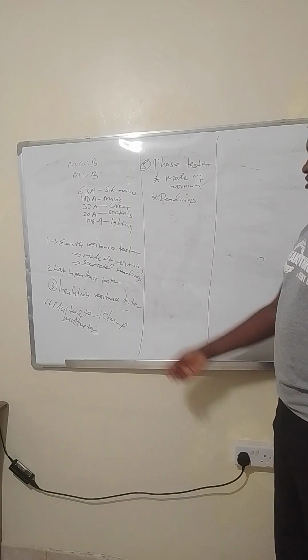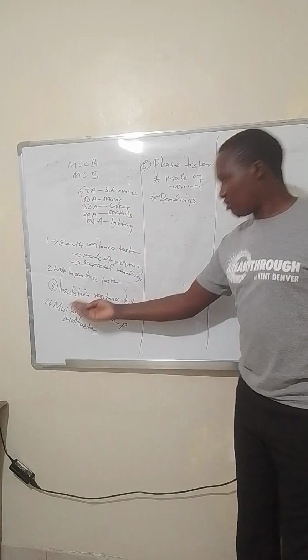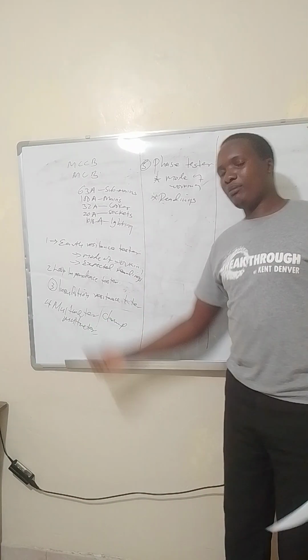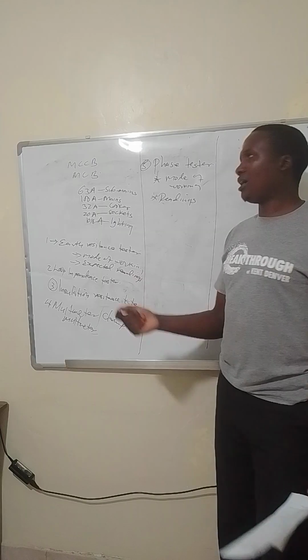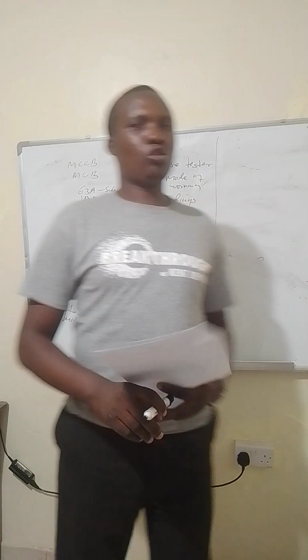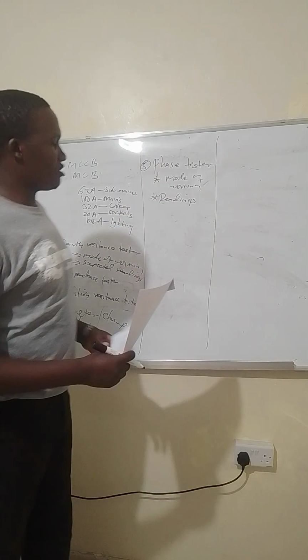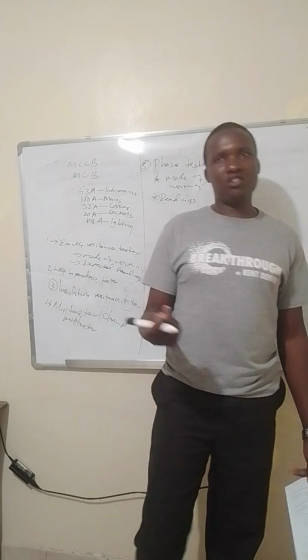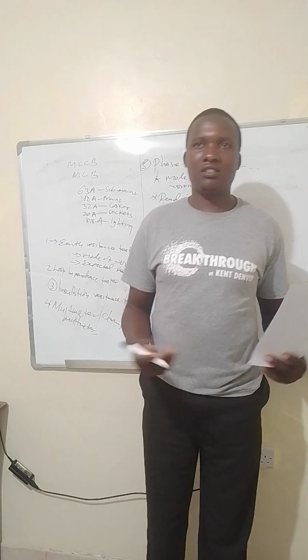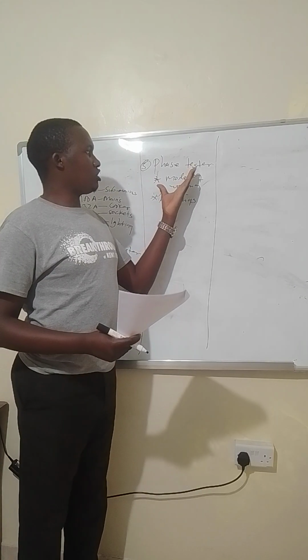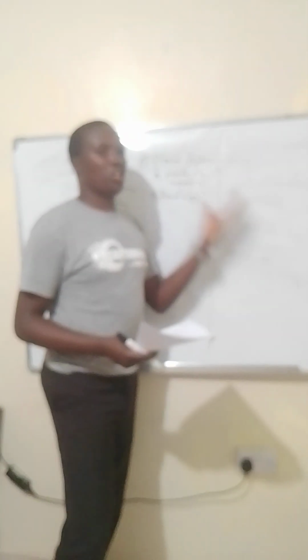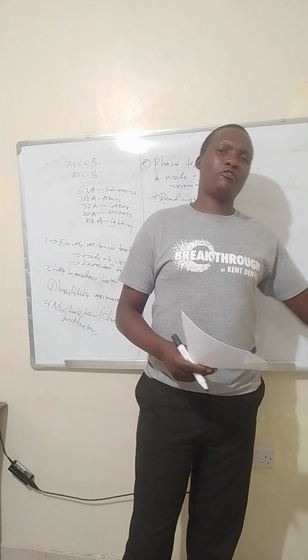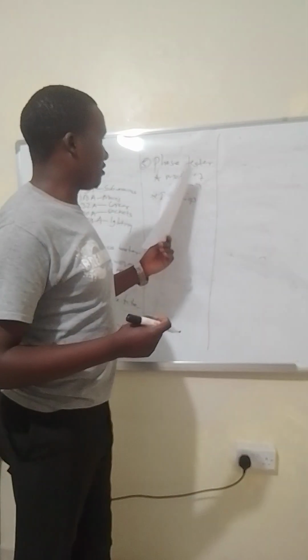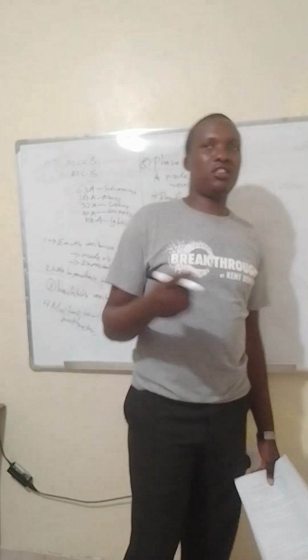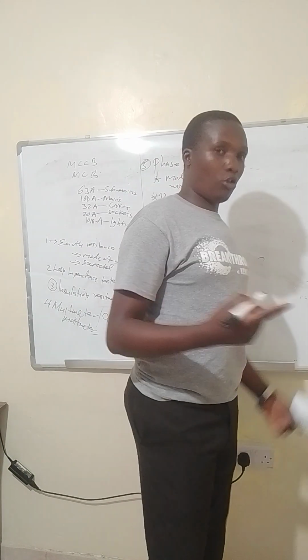We have earth resistance tester, we have loop impedance tester, we have insulation resistance tester, we have multimeter or clamp multimeter. They work hand in hand. We have phase tester. So you need to know very well the function of a phase tester. A phase tester is to check if there is a fault in one phase or there is a forward or reverse. It can check if there is a fault in electrical phase, or it can check if the motor has been mounted in forward or reverse. So this works in 2 dimensions. Number one, as I've said, to check the fault phase. Another thing, to check whether the motor is running back or forward.